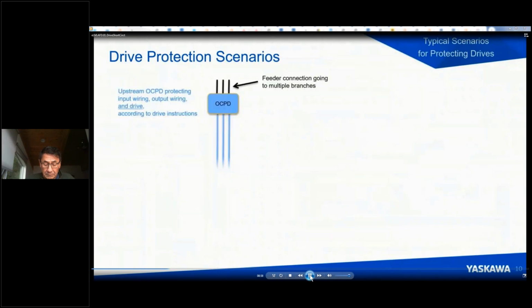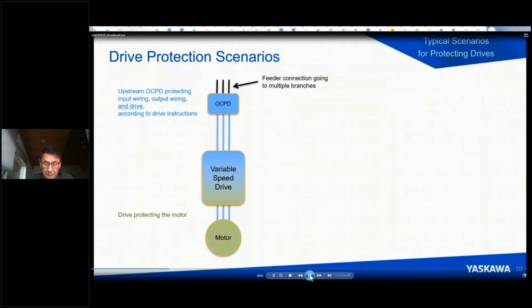So let's look at a couple different drive protection scenarios. In the first case, we've got a feeder circuit that's feeding an overcurrent protective device that is then connected to the drive and to the motor. In many cases, that overcurrent protective device is protecting the drive, and there's actually nothing else that's required. How do you know this?